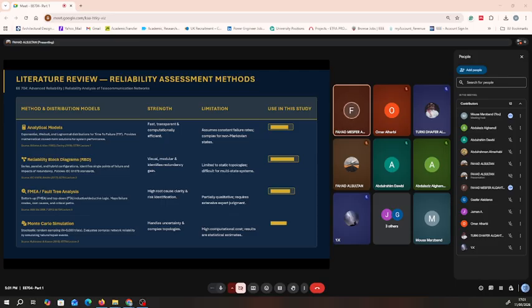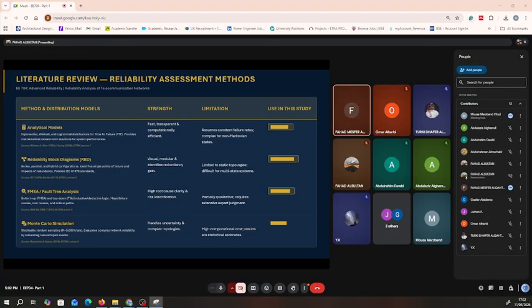Its limitation is that it assumes constant failure rates and is complex for non-Markovian states. The second method is RBD, the reliability block diagram, using series, parallel, and hybrid configurations, which identifies single points of failure (SPOF) and the impact of redundancy, related to standard IEC 61078. Its strength is being visual, modular, and identifying redundancy gains, but its limitation is being restricted to static topologies and difficult for multi-state systems.